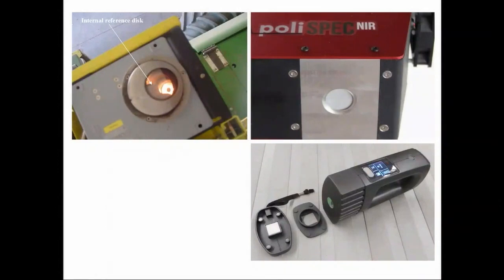The way that instrument manufacturers compensate for that is something called referencing. Depending on how the instrument is designed, the referencing might be built into the instrument, like is shown here at the Harvest Lab in this poliSPEC, or it might be an external reference that you apply to the instrument. There are pros and cons to different ways of referencing, but it's important to work with an instrument that uses this reference regularly to compensate for dark current, because all of these instruments have that problem. Some more expensive laboratory and advanced instruments actually try to cool the diode array to maintain the temperature internally. I would say that most handheld NIRS devices don't do that, more as a cost consideration.